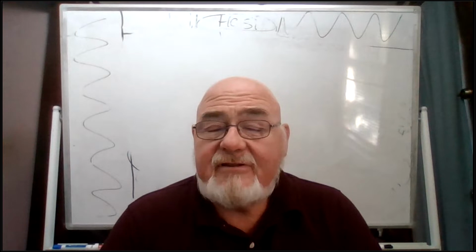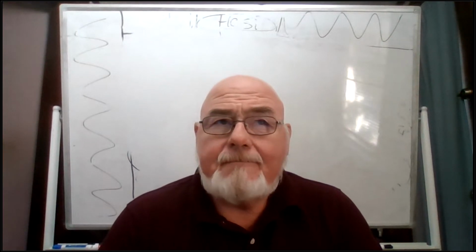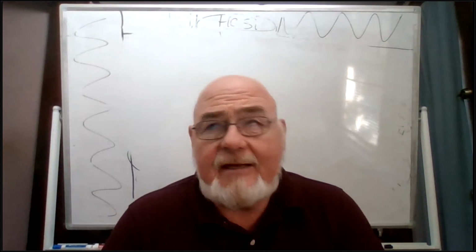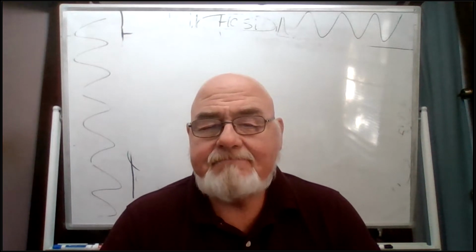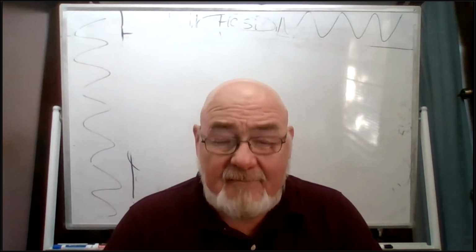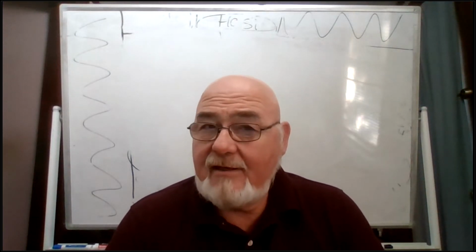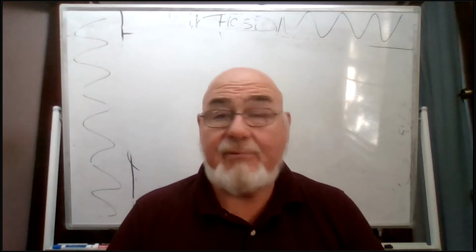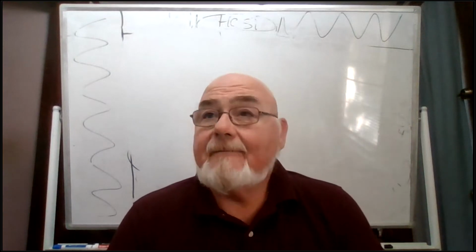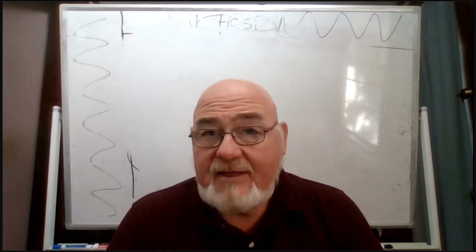But a lot of it, again, conversions are kind of a big deal. And in areas, linear measurements, areas, and volumes, I work in cubic feet, which is what we mostly work in. And then there are certain conversions that are going to be tattooed on your brain, like 7.48 gallons per cubic foot, 8.34 pounds per gallon. Another one is 0.433 psi per foot.